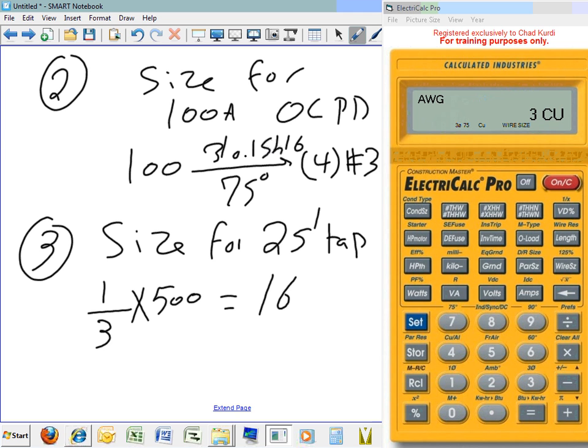166. With a... doesn't it go to 166.6? Yeah, it's going to have a repeating decimal. I'm just going to go 167. Yep, 167. Right? Because it's more than a half, round up. 167. This is the minimum conductor size that you can size. You can pull 25 feet minimum.